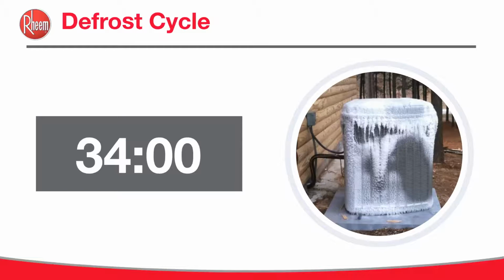The defrost will terminate at 14 minutes, again, 14 minutes, or after the outdoor coil has reached the predetermined settings as per the dip switches. From the factory, it's at 70 degrees Fahrenheit, but it can be 60, it can be 80, depending on your location. Most people leave it at 70 just because it seems to work there. There is a predetermined delay before the compressor is re-energized in heating mode as well. So that's defrost, which is something that you have on heat pumps, sorry, but you don't have on air conditioning.